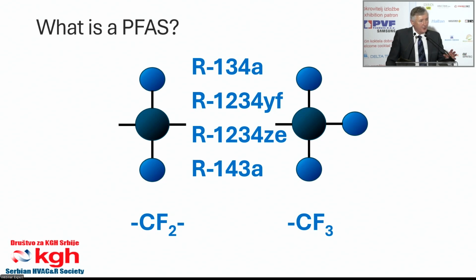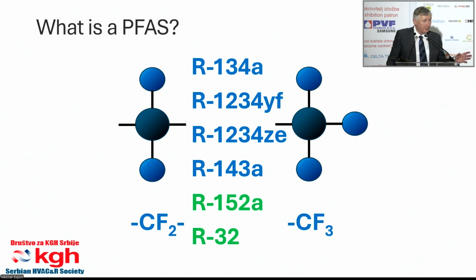So a lot of these refrigerants that we've been familiar with and used to using are now coming under fire, with new regulations being developed specifically about the products of degradation, and this creates great uncertainty with regard to what is actually going to be available in 5 years' time, 10 years' time, 15 years' time. Interestingly, 2 refrigerants here have been quite widely used either as single components or as blends. R152A you're perhaps not so familiar with. It was originally proposed as a replacement for R134A in car air conditioning systems, mobile air conditioning.